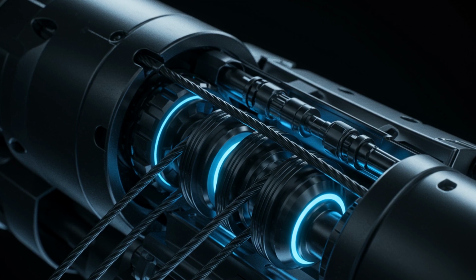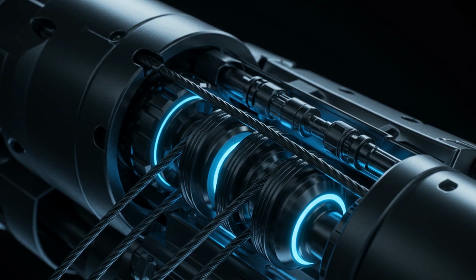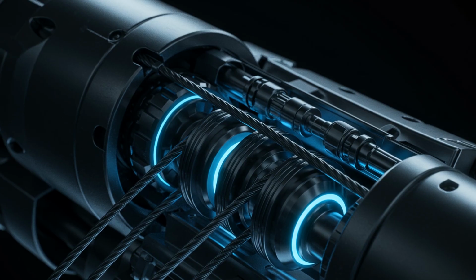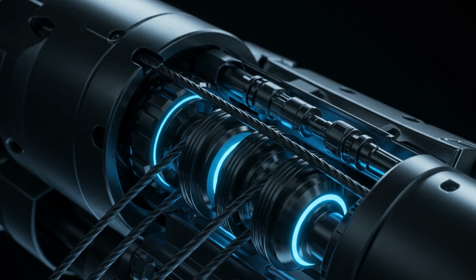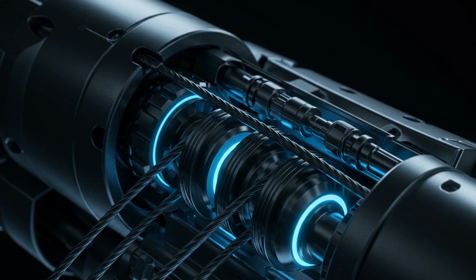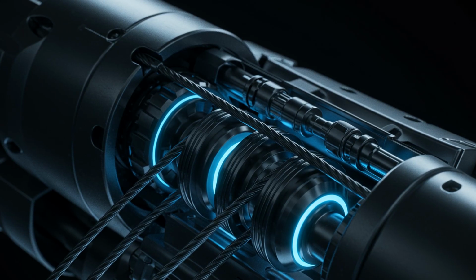To prevent this, sensors continuously monitor the tension in every line. The assembly of these cable systems is one of the most labor-intensive parts of the build, requiring technicians to hand-string the cables through the joints, much like stringing a high-tech instrument. These tendons allow the wrist of the robot to rotate 720 degrees, far beyond the capability of any human surgeon, allowing for angles of entry that were once thought impossible.